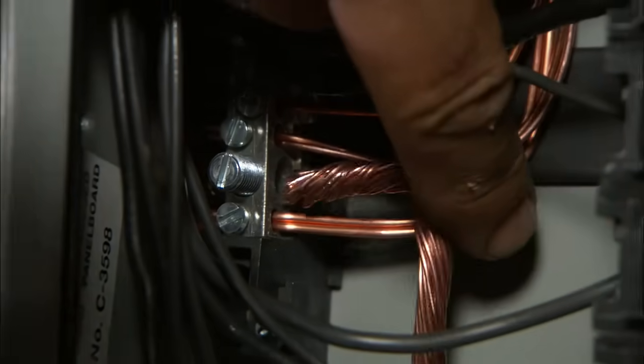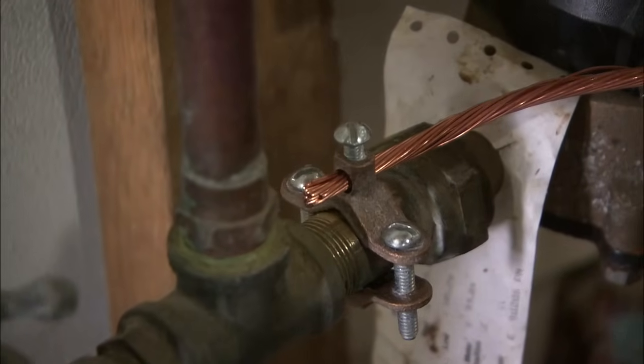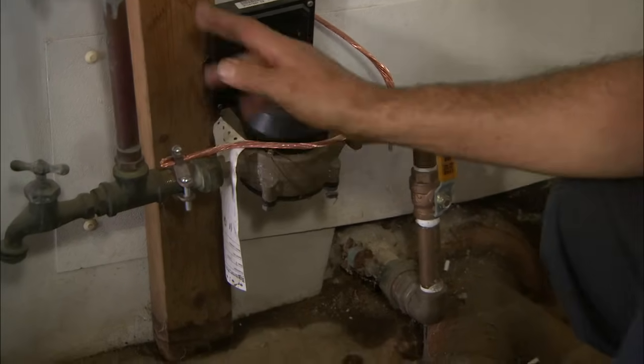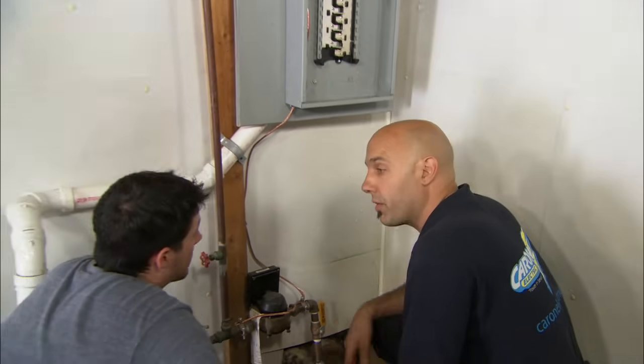This is your main ground wire. It runs out through the bottom of the electrical panel and ties onto the copper water main that comes in from the outside. There's a clamp that runs over and jumps your water meter and ties to the other side, so that if the water meter ever gets removed, you'll always have this important ground.